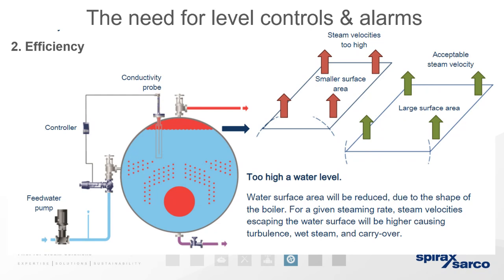So if you've got wear and tear from acid buildup, acid tends to be formed when you have air entering a system before the trap, and you also have a higher than normal velocity through the trap. So that added velocity where it hits corners, plus the fact that you've got carbonic acid there, wears certain trap materials faster. So if you've, say, got an SG iron trap or a cast iron trap, you'd see that fail quicker than a carbon steel or stainless steel.